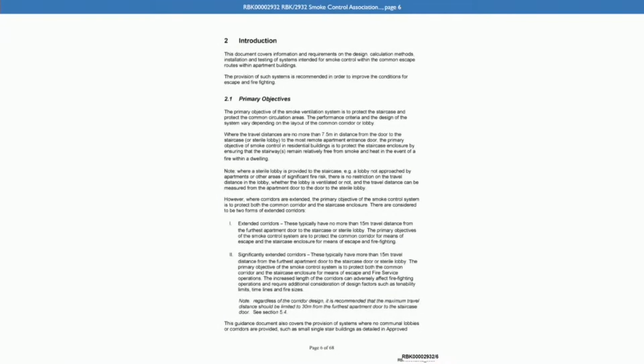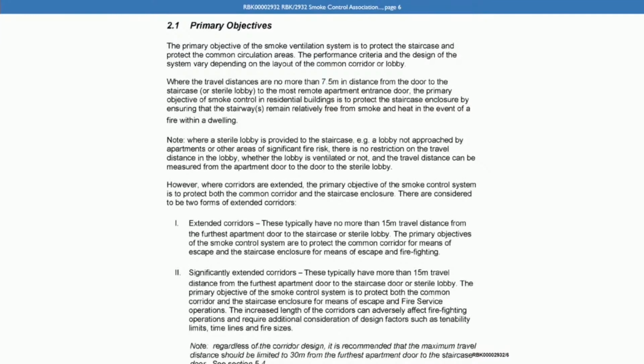If we go now to the 2015 version of the SCA guide, which is RBK00002932, page 6. Now, we've heard the evidence, and you've said in your report that it's the 2012 guide that would have applied to the assessment of the smoke control system, but the 2015 guide expresses the principle as well, which is why I've taken you to it. It says at the beginning of the section titled Primary Objectives, where the travel distances are no more than 7.5 metres in distance from the door to the staircase, or sterile lobby, the most remote apartment entrance door, the primary objective of smoke control in residential buildings is to protect the staircase enclosure by ensuring that the stairways remain relatively free from smoke and heat in the event of a fire within a dwelling. And it goes on to say, however, where corridors are extended, the primary objective of the smoke control system is to protect both the common corridor and the staircase enclosure.